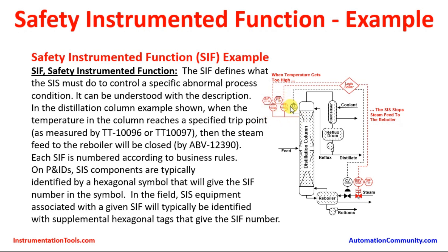Whenever there is over-pressure or high temperature in the column, two additional temperature transmitters — shown in red — are part of the Safety Instrumented System. These two temperature transmitters sense the temperature inside the vessel and send signals to the SIS logic solver. From the logic solver, the output goes to the EBV — emergency block valve. Here, the SIS stops the steam feed to the reboiler whenever the temperature inside the column exceeds the pre-set limits.